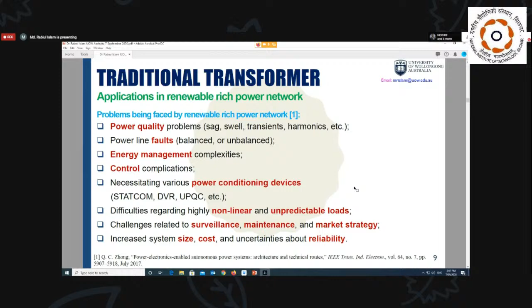So here I want to introduce another challenge that our transformer may suffer from. For example, especially if we talk about large penetration of solar power, then what will happen? Solar power feeds into the grid through a power electronics converter or inverter. If you analyze the output power of the solar PV inverter, you can easily realize that the inverter is not only injecting AC power, it is also injecting some DC components or power.